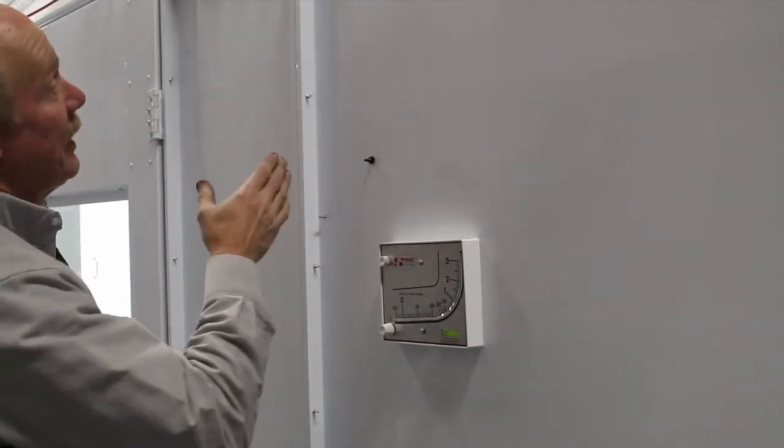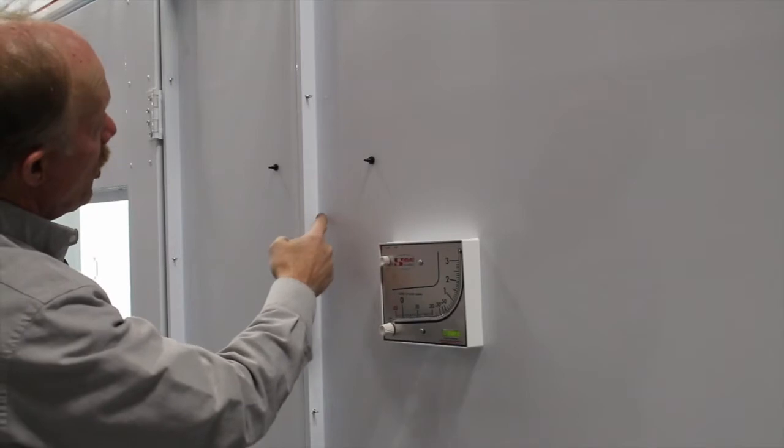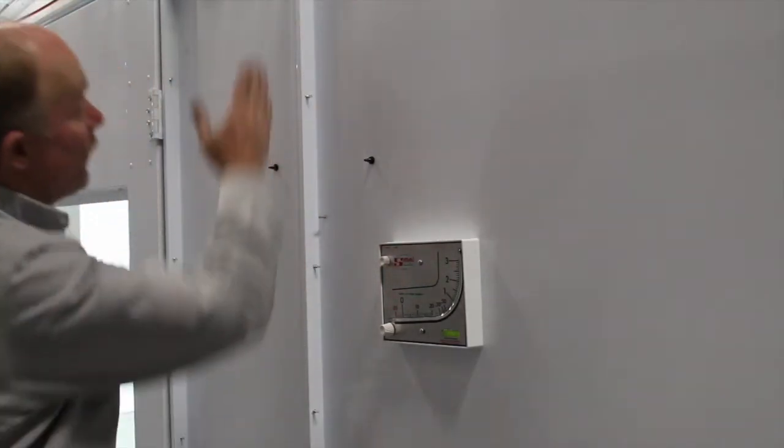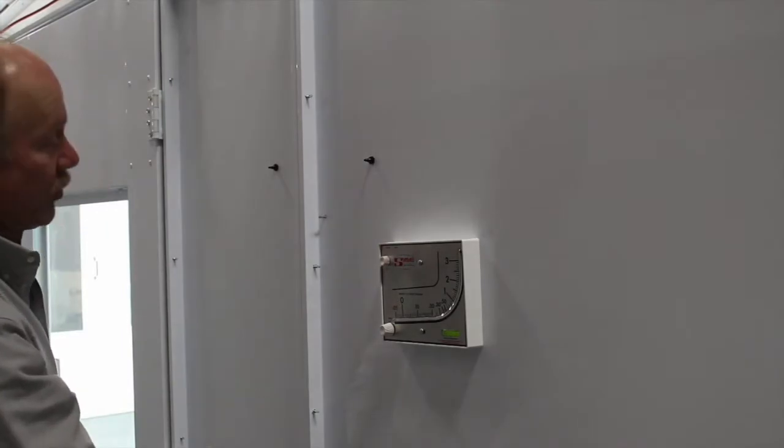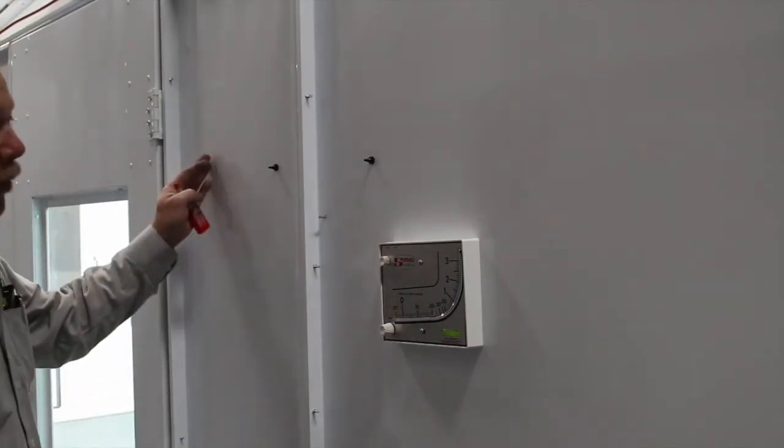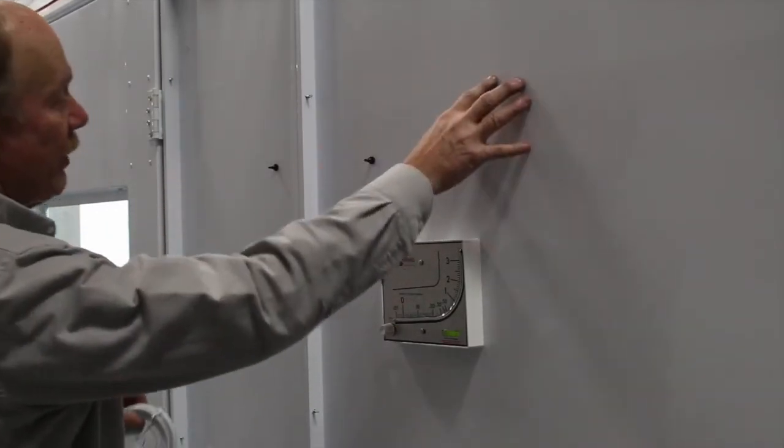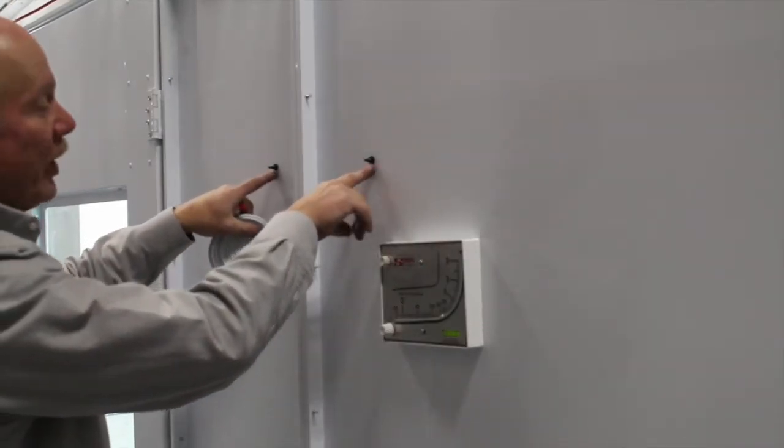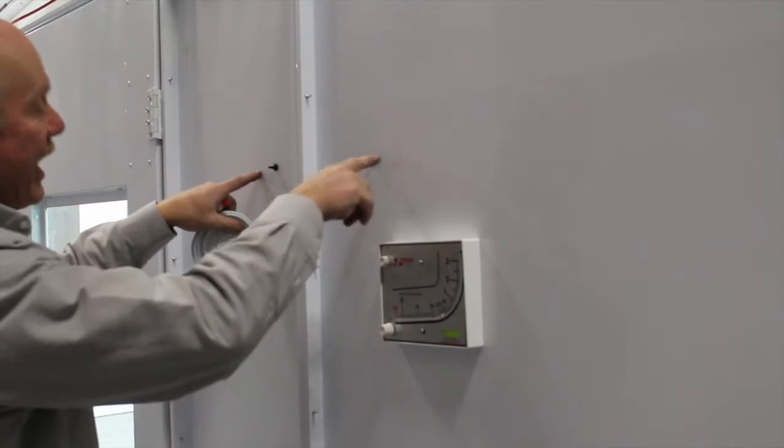You have to locate the filter wall. You can locate it by the screws that are protruding from inside coming out. This line here is where your filters are. This is before the filters. This is after the filters. And these are the two nipples that we installed to read before and after the filters.